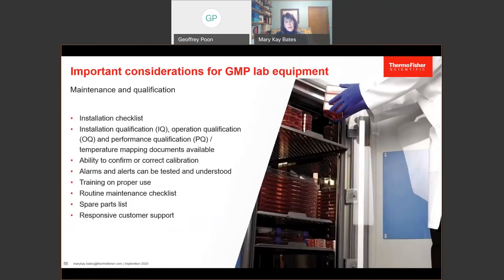You should look for a provider that ensures they provide tests to perform. They will provide tests that will confirm elimination or neutralization of the chemical and also elimination of the microorganisms, in other words, proving that it's effective. What else should you consider in thinking about lab equipment for your GMP processes? What about maintenance and qualification of that equipment? How do you install the equipment? How is the qualification for installation, operation and performance, including temperature mapping, how is that performed? Is there someone trained on this equipment to help? How do you check or change calibration? How do the alarms work? What's best practice for using this equipment? What about replacement parts? If you need manufacturer support, would it be available when you need it?